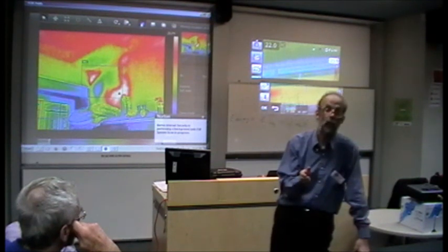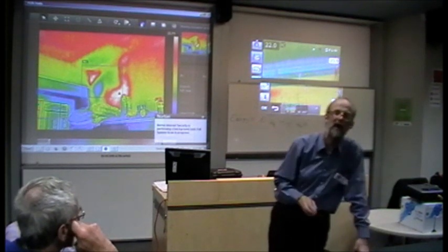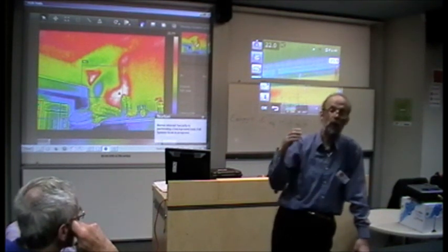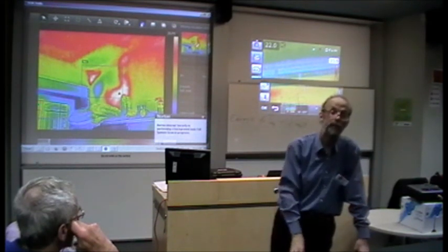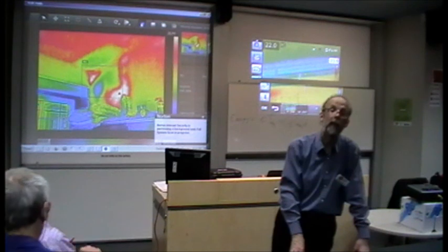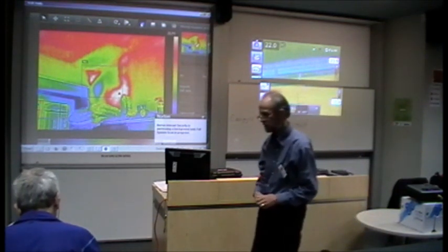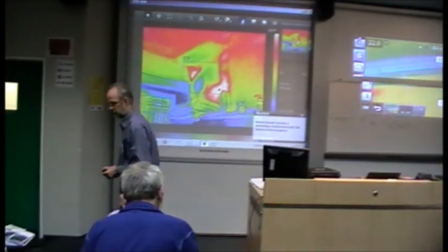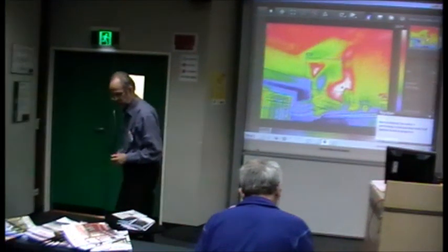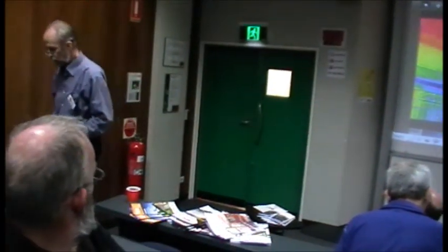Although there is some cooling effect of the wind just over a surface, it's not enough. But either a hot windy day or a cold windy day will be a good day to get a good idea of pure heat loss from a house, like insulation breakdowns or thermal bridging. Could you heat the house a little above where you normally would, and then image it at 5 or 6 o'clock in the morning before you had any influence from the sun?